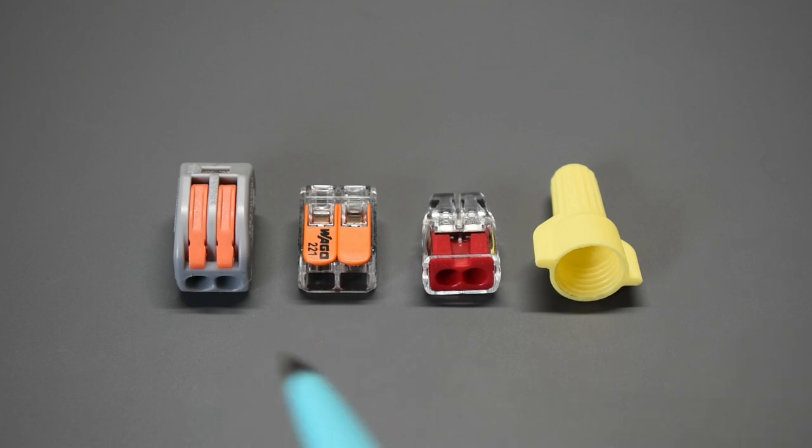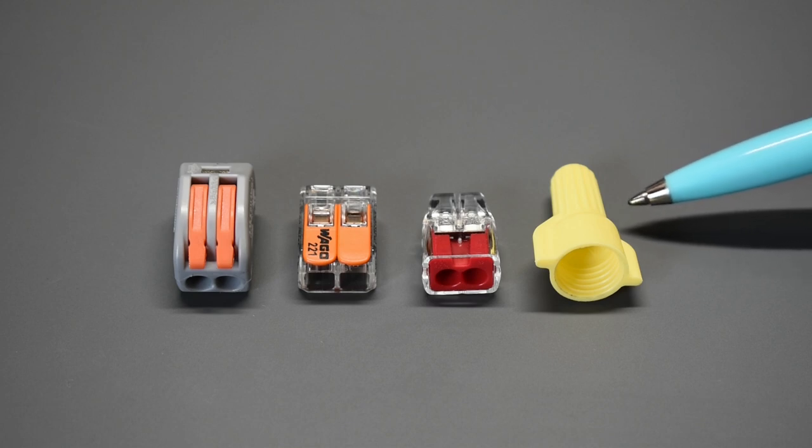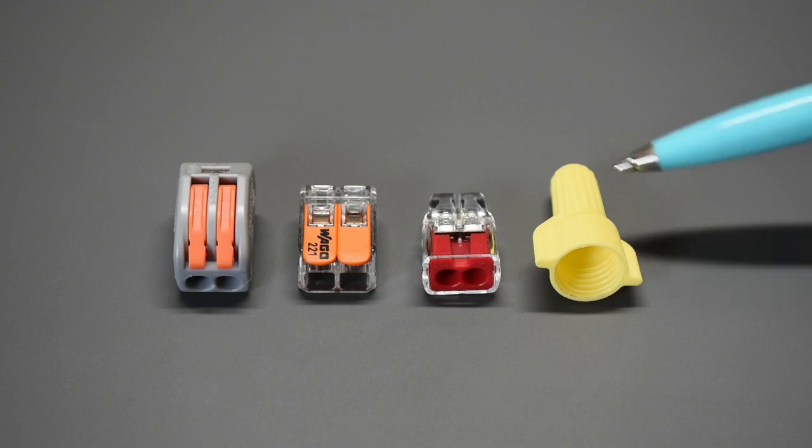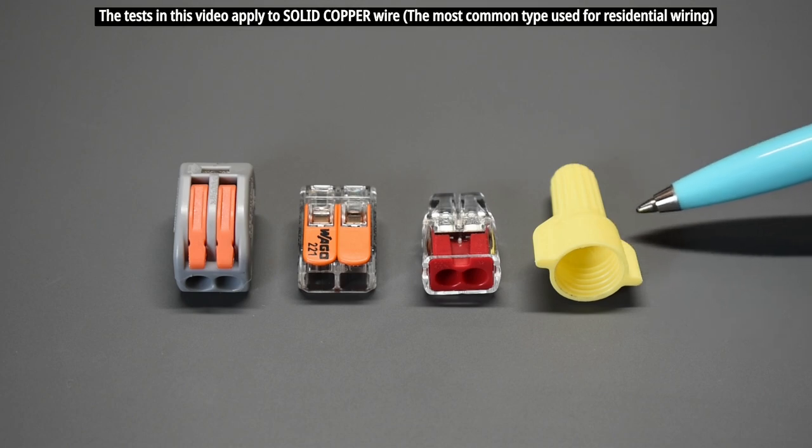So in today's video, we're going to be putting each one of these connectors to the test. I'm going to be using the same testing method that was shown in a previous video. I'll use identical lengths of number 12 solid copper wire and place a constant load on each connector for 15 minutes. It's going to be a high current load, around 18 amps.